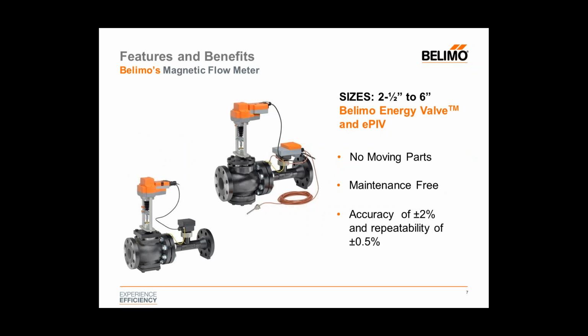Let me talk to you a little bit now about some of the features and benefits. These features and benefits carry across to both the ePIV and the energy valve. What we're talking about here is the flow sensor. One of the most attractive benefits of the flow sensor is that it has no moving parts, unlike a paddle or impeller type or wheel type flow sensor. Those impellers could be clogged with debris within the system and produce inaccurate flows or, in the worst case, stop operating. These have no moving parts, so they are much less sensitive to debris within the system. These sensors themselves are completely maintenance-free. They are calibrated before they leave the factory and do not require recalibration in the field.